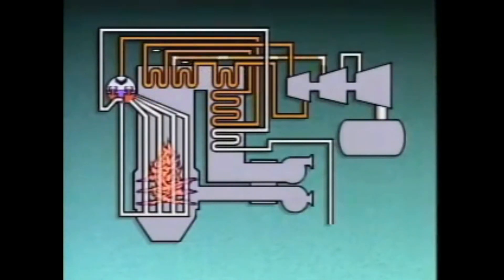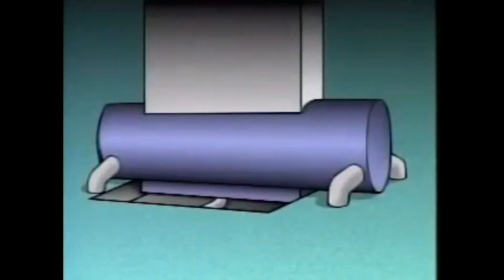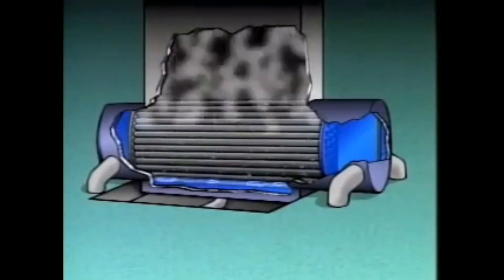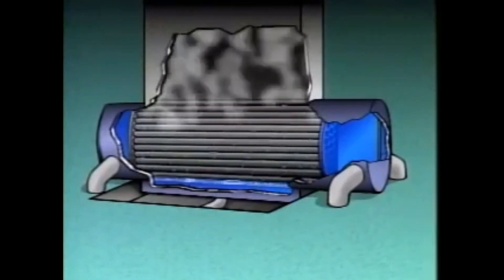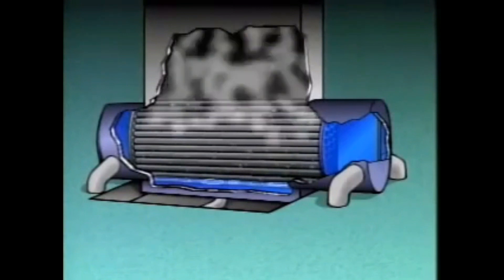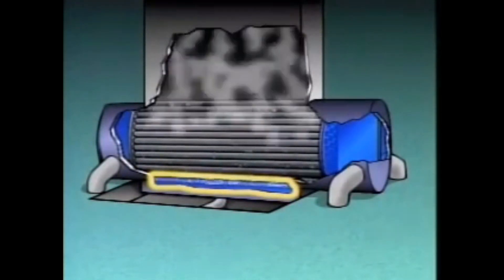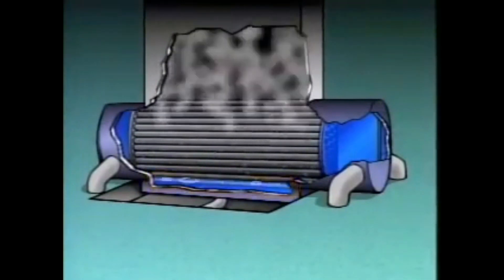After it is reheated, the steam flows to the intermediate pressure, or IP, section of the turbine, and then through the low pressure, or LP, section. From the low pressure section, the spent steam flows into the condenser. Inside the condenser, the steam flows over tubes that contain cooling water. The water in the tubes absorbs heat from the steam, and the steam condenses back into water. The water is collected in the bottom of the condenser and pumped back to the boiler to begin the cycle again.